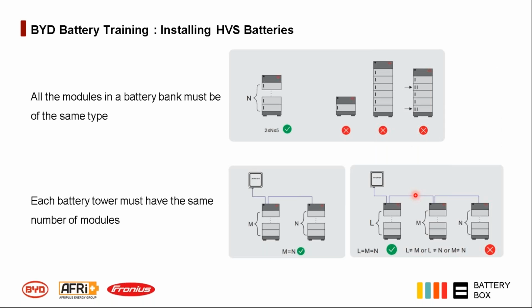Some practical applications of the tower design. When putting HVS towers in parallel to increase the size of your battery bank, you must always ensure you have the same number of modules in each tower, and that the types of modules are all the same. The HVS and HVM have the same box module, but the difference is they've got either a 1 number or a 2 number on them. It's very important not to mix HVS with HVM in any bank.